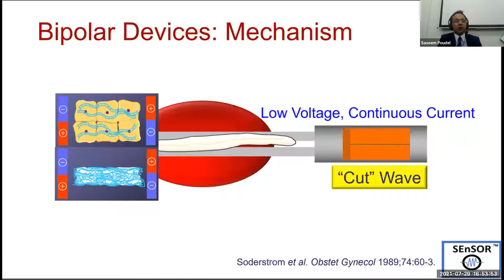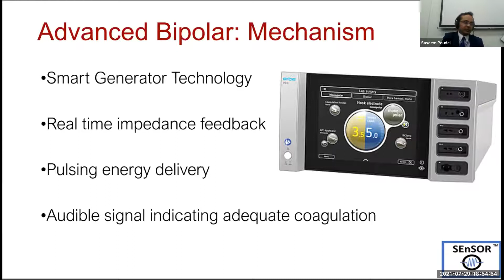With advanced bipolar, we have a smart generator technique that receives real-time impedance feedback from the tissue and controls how much current and power goes through the active electrode, to give us very good coagulation. It also has a pulsating energy delivery system so that the electrode does not get overheated. It is designed to keep the temperature of the tissue between 60 and 80 degrees Celsius. It rarely gets above 80 degrees Celsius. This is the ideal setting for coagulation. Most of these devices also have an audible signal indicating that adequate coagulation has happened, so that users don't overuse it.